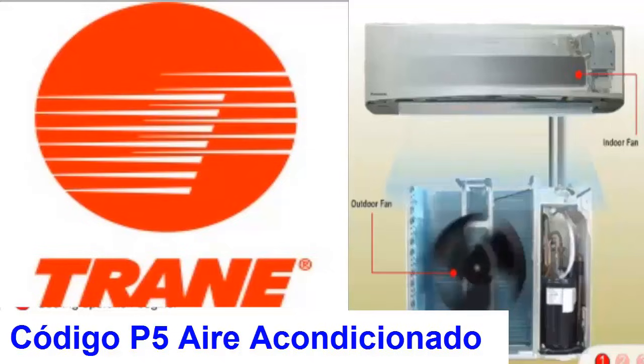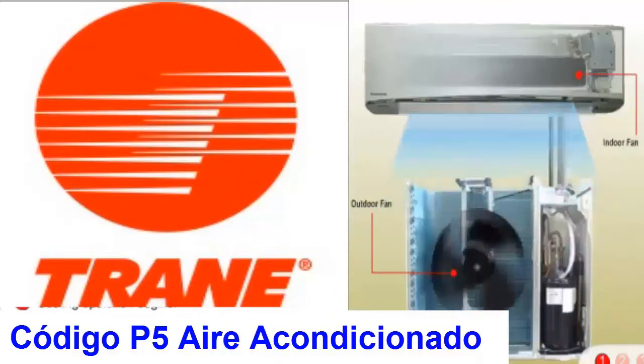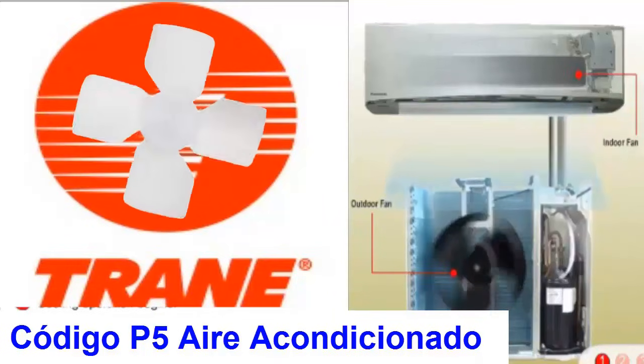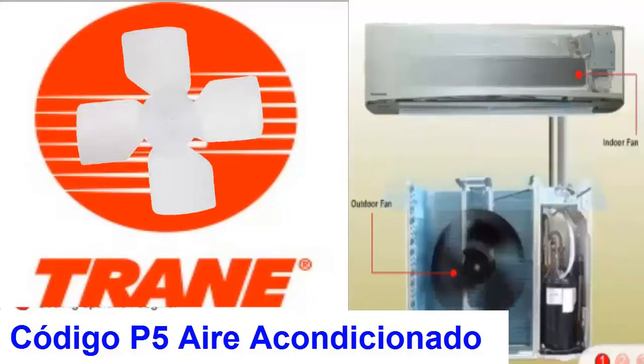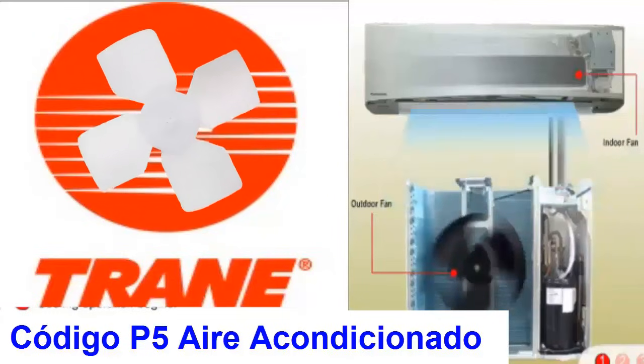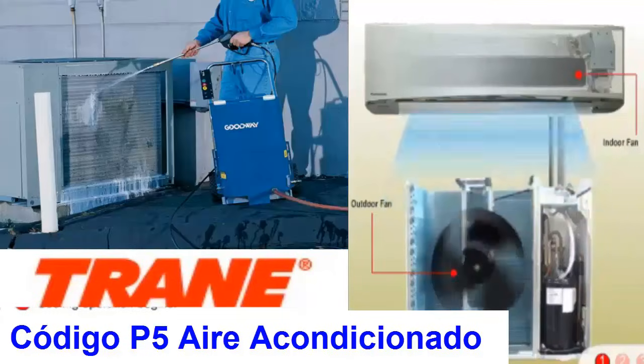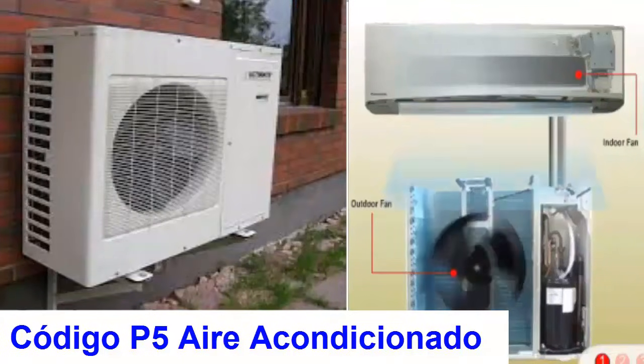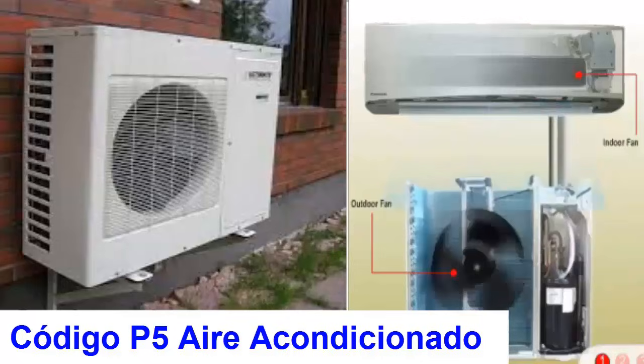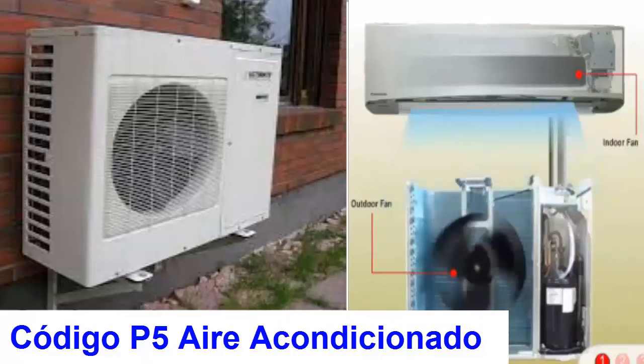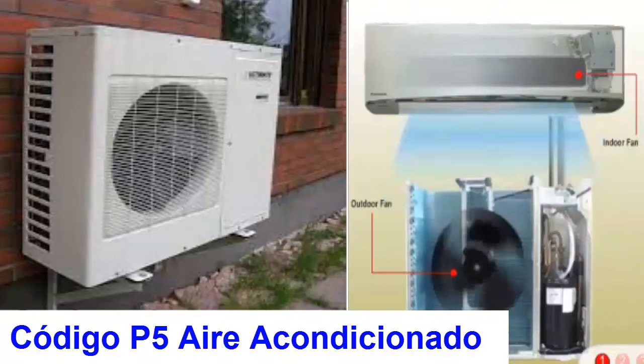3. However, for other Trane models, the P5 code indicates a malfunction or high temperature protection of the condenser. It is crucial to observe the proper operation of the external unit fan and check the cleanliness of the condenser. Special attention should be paid to the condenser heat exchange and ensure there are no obstructions that could cause overheating.